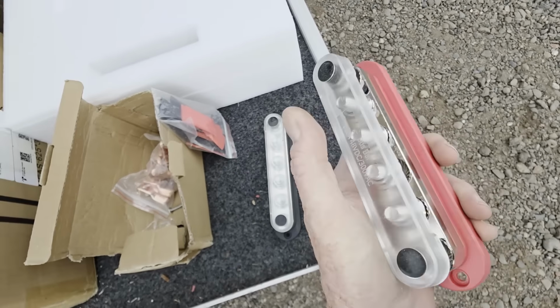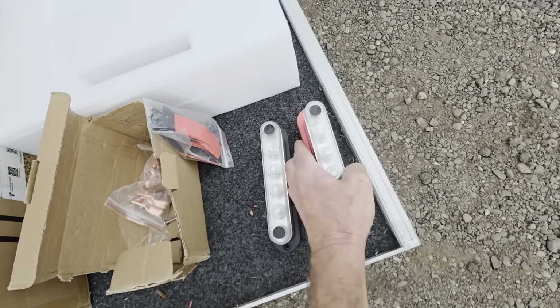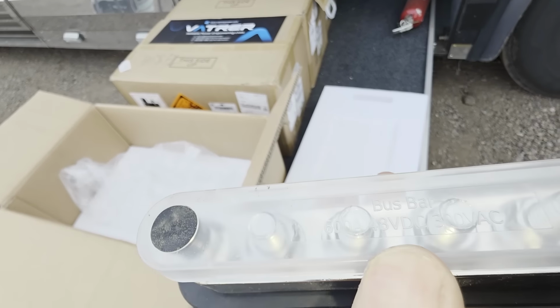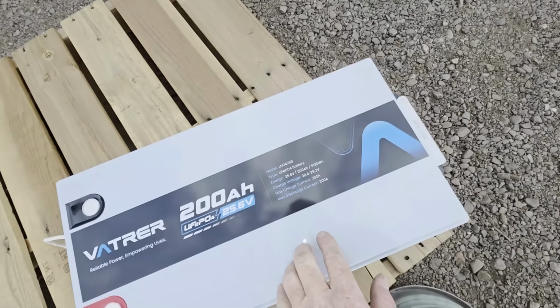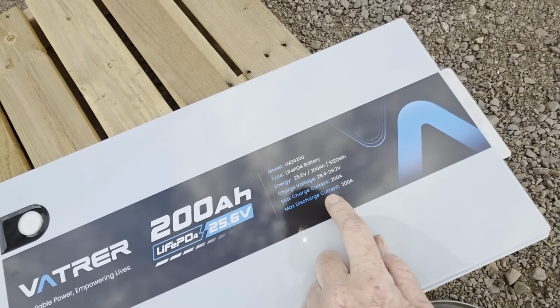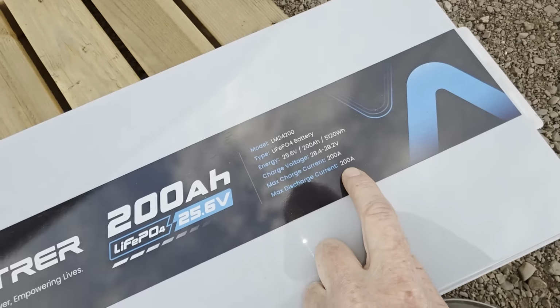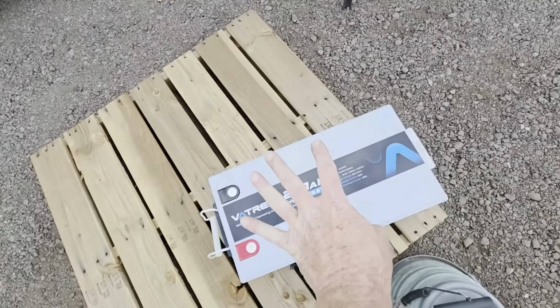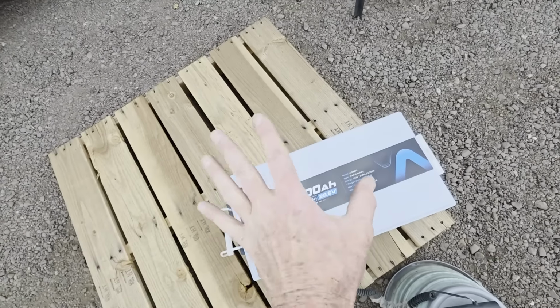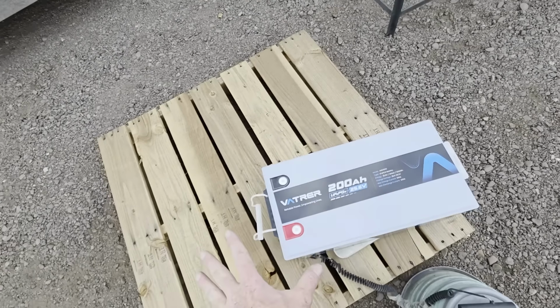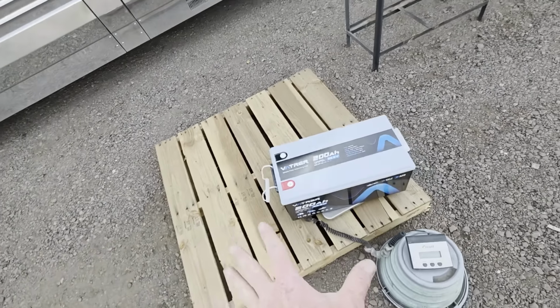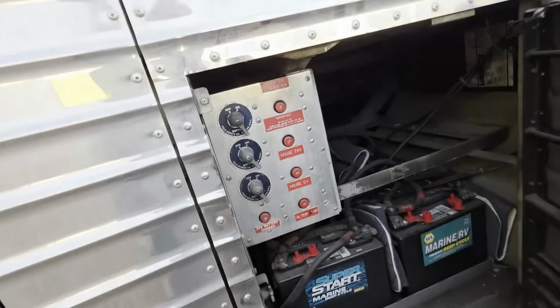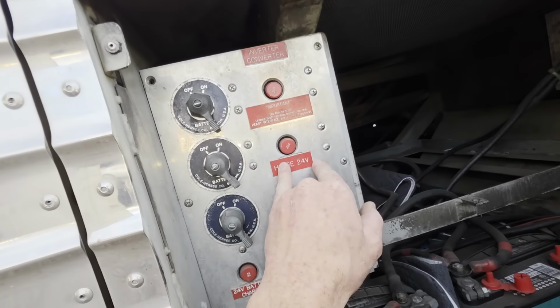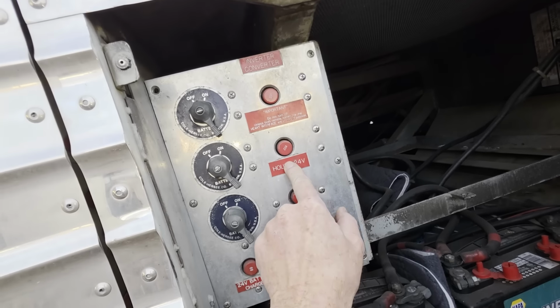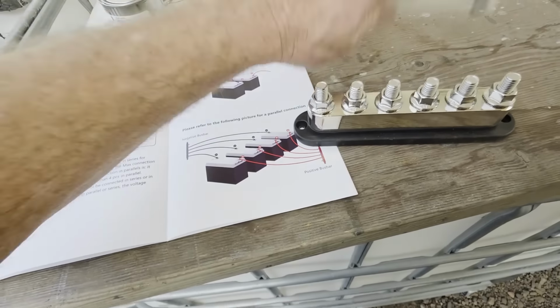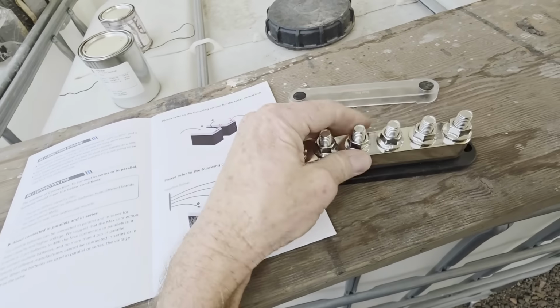So these bus bars are rated about 600 amps of continuous use at 48 volts. Because these batteries do have a maximum charge and discharge continuous current of 200 amps apiece, and we have 4 of them in parallel, we could have 200 amps coming off of each one of the 4 batteries. So I mean to make sure the bus bar can handle that load, even though the overcurrent protection is going to be maxed out at about 200 amps maximum, which I have no doubts this can handle.